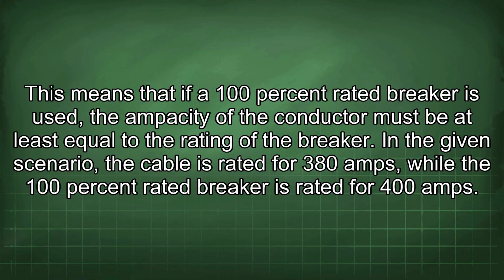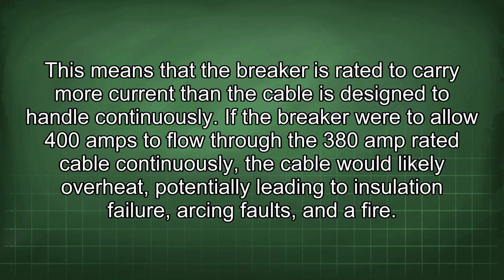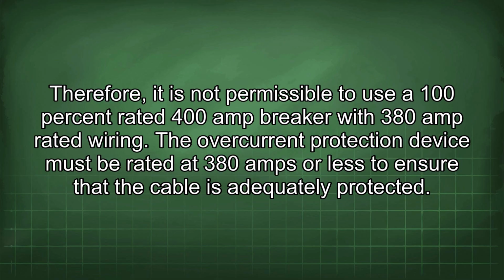In the given scenario, the cable is rated for 380 amps, while the 100% rated breaker is rated for 400 amps. This means that the breaker is rated to carry more current than the cable is designed to handle continuously. If the breaker were to allow 400 amps to flow through the 380 amp rated cable continuously, the cable would likely overheat, potentially leading to insulation failure, arcing faults, and a fire. Therefore, it is not permissible to use a 100% rated 400 amp breaker with 380 amp rated wiring. The overcurrent protection device must be rated at 380 amps or less to ensure that the cable is adequately protected.